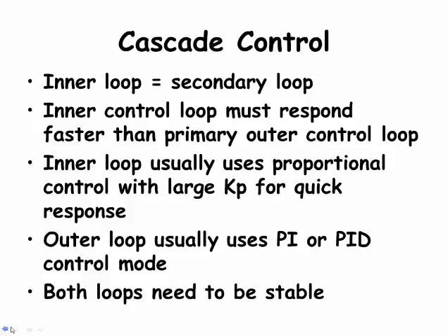Cascade control can be used when there is some internal process information that can be used to make a process adjustment. Using the internal process information means that changes can be made sooner than waiting for the process output to change and indicate an adjustment. By combining feedback control with cascade control, the overall process response can be more stable and faster responding than a conventional single-loop feedback control system.